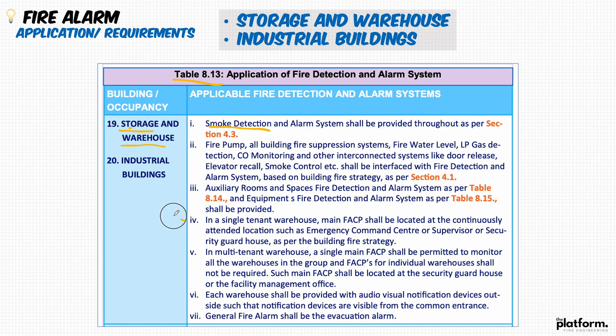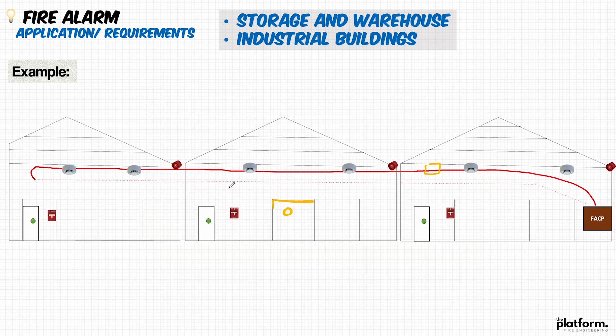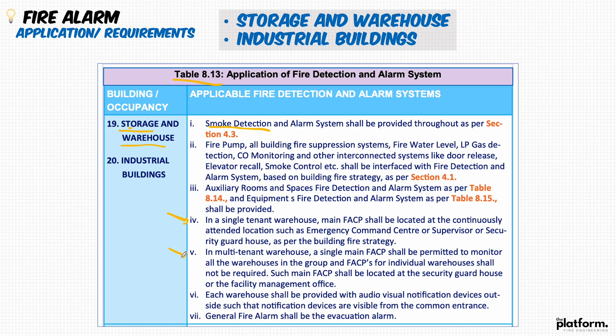For a single tenant warehouse, the main fire alarm control panel shall be located at a continuously attended location — such as an emergency command center, supervisor room, or security guard house — as per the building fire strategy. If you have only one storage or one warehouse and you consider it as a single tenant, then you need to install the fire alarm system and it should be in a continuously attended location.